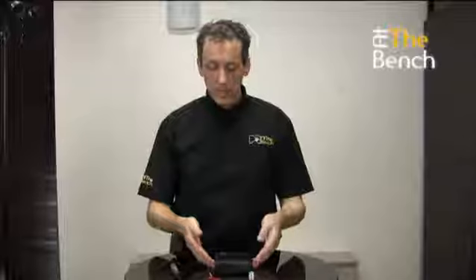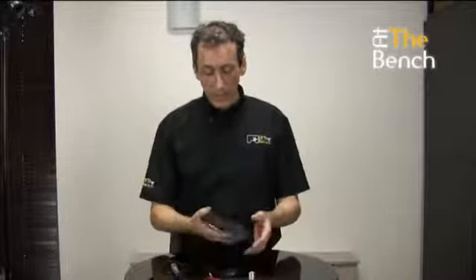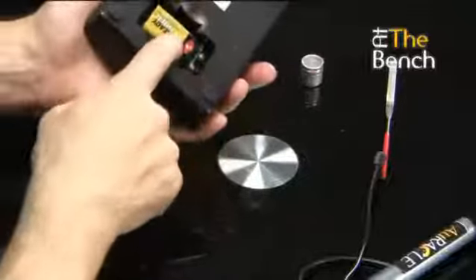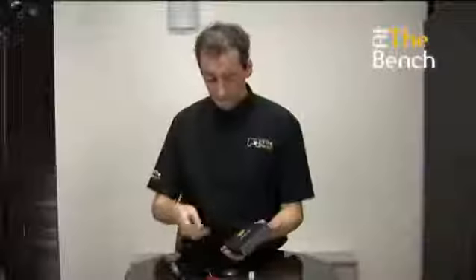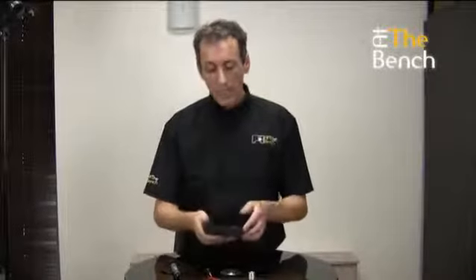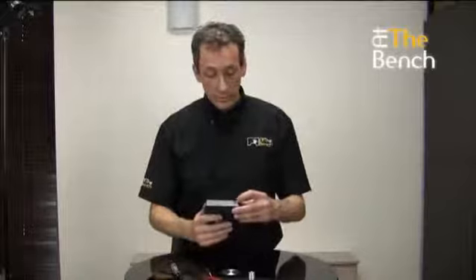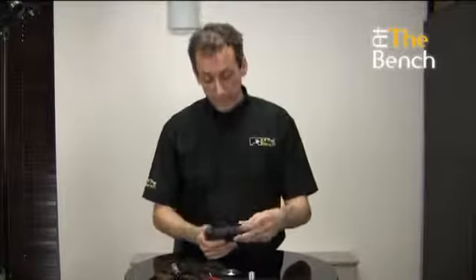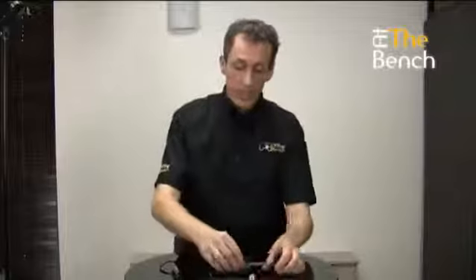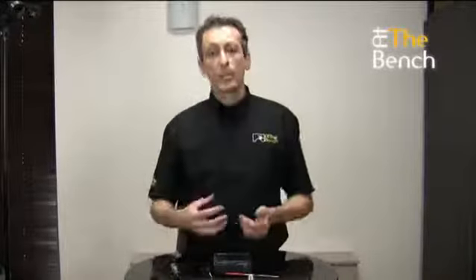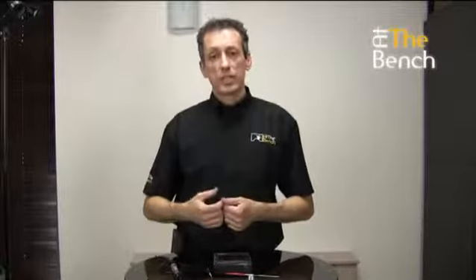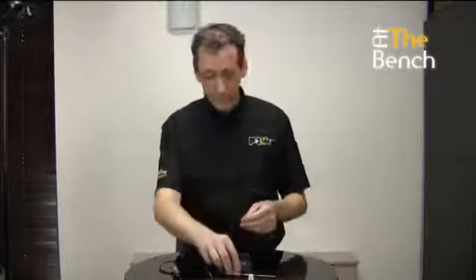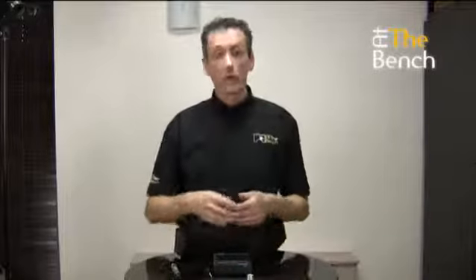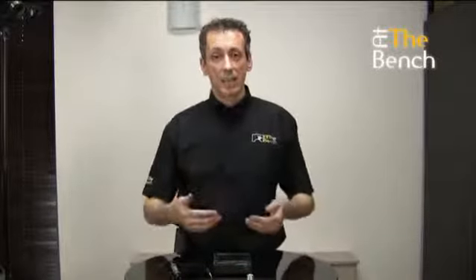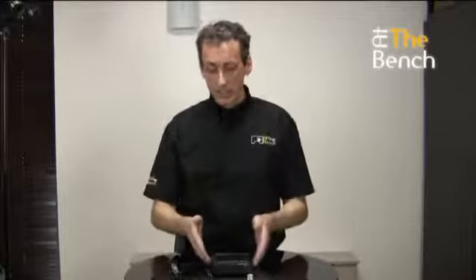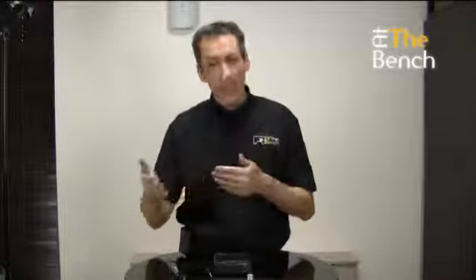The unit can be powered in two ways. It can be powered by the internal 9-volt battery that slips into the bottom here, or an optional external mains power adapter that plugs into the top of the machine there. So the first thing that we need to do is to calibrate the machine. Every time you turn the machine on, the machine has to be calibrated. If you leave the machine on throughout the day, well then it always pays to calibrate the machine throughout the day, just in case the result will vary slightly.